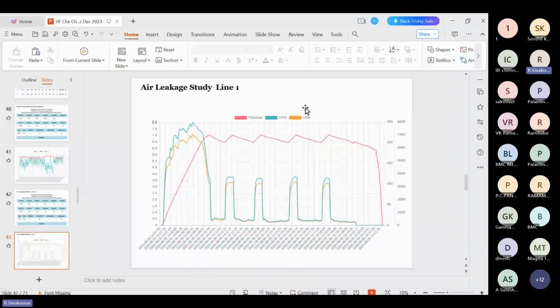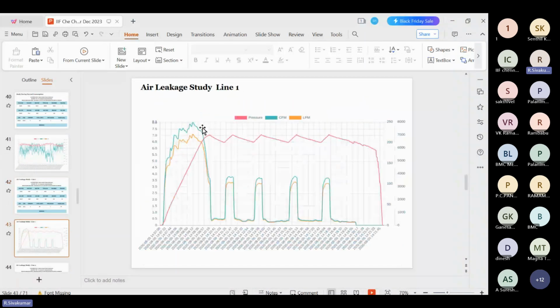So this is the air leakage study. The earlier one was the air leakage study in the same plant. During that time, for almost half an hour, the entire operation was stopped. So this indicated a pulse wave kind of waveform. This is the energy loss due to the air leakages. If we put the power analyzer, we can quantify how many kilowatts were lost due to this air leakage. So this tool will be helpful to the industry.